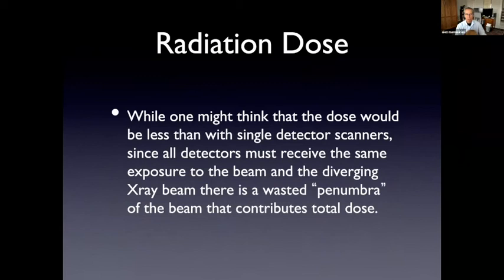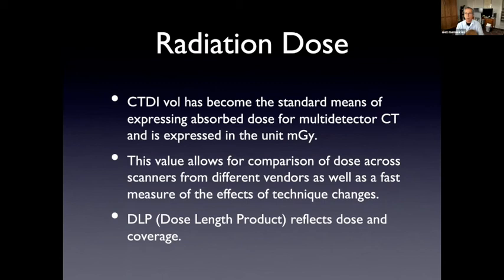Coming back to this idea of dose, because all detectors receive the same exposure and this wasted penumbra, oftentimes single slice scanners have a lower dose. Now, how do we measure dose? It's a little complicated, but I will just bring to your attention this term, it's called CTDI volume. In the US, pretty much all the scans have to display the CTDI volume or the DLP. You should be familiar with these terms. This has become a standard means of expressing absorbed dose. Now, this is not a measured value. There's not a detector in the scanner that registers the actual dose. It's a calculated value, but it's a pretty good unit.